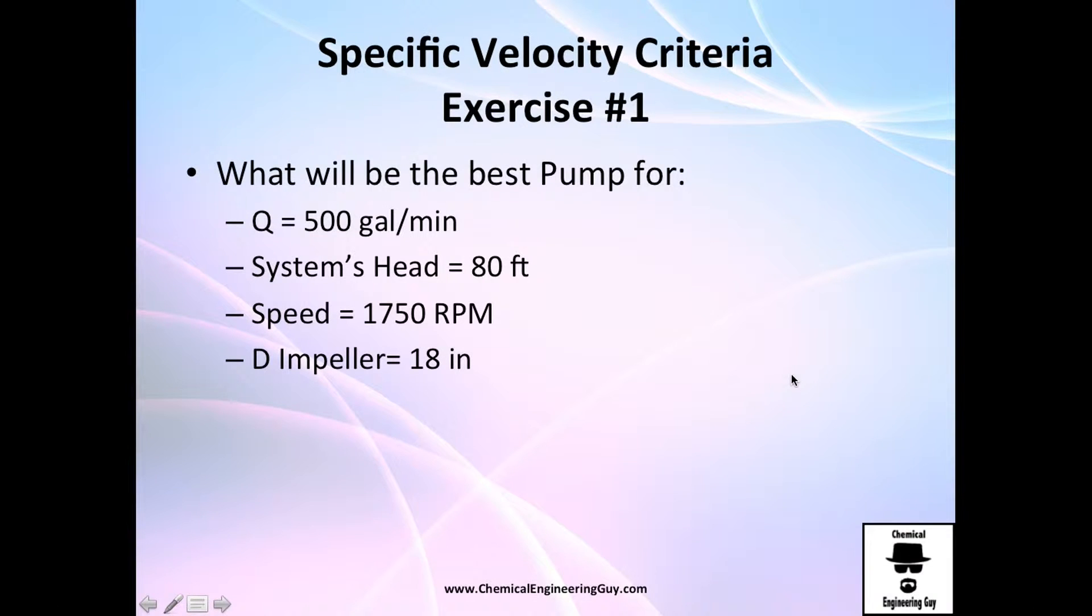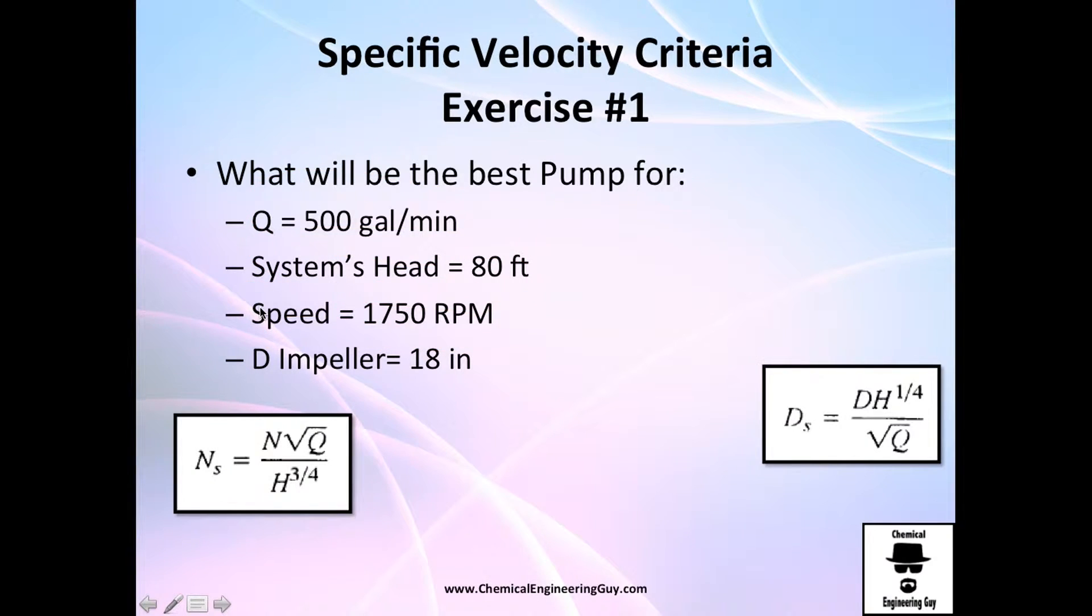So for exercise number one, I want you to find the best pump for this process, which is 500 gallons per minute. The system head is about 80 feet and the velocity of the impeller is 1750 revolution per minute. The size of the impeller is 18 inches. So what we need to do is essentially just plug the numbers in and be sure to use RPM here, gallons per minute here, and the head use feet. Here use inches.